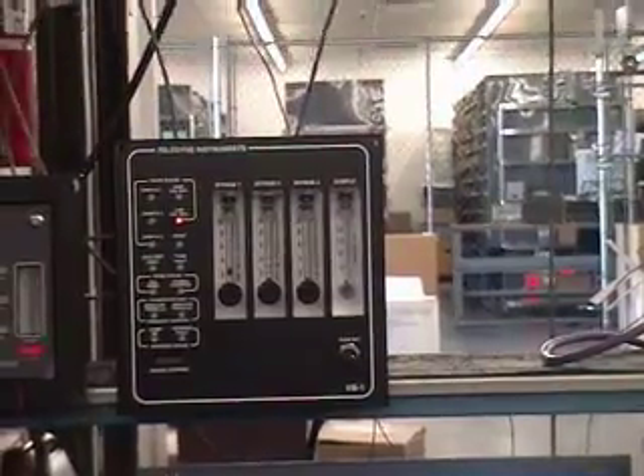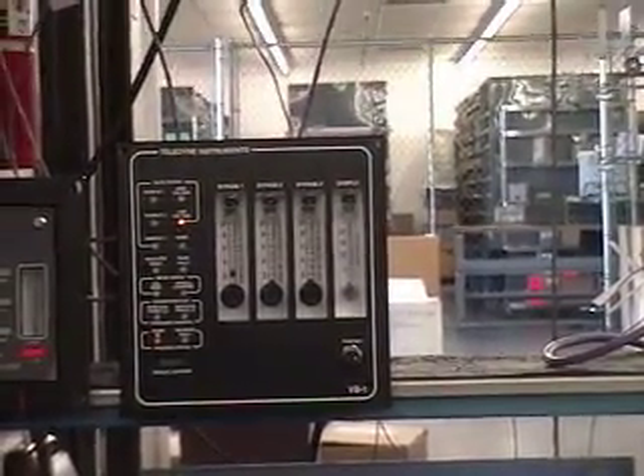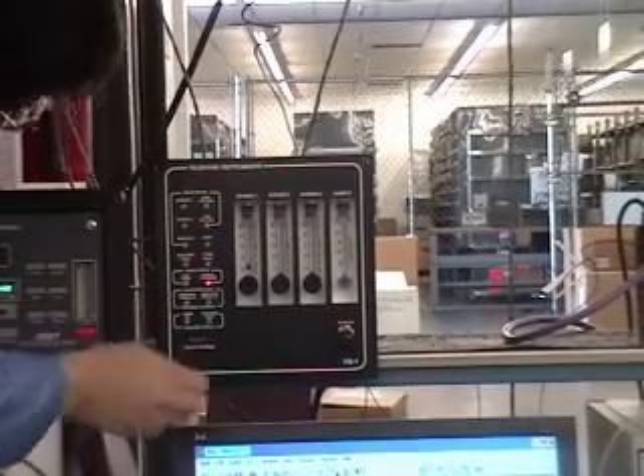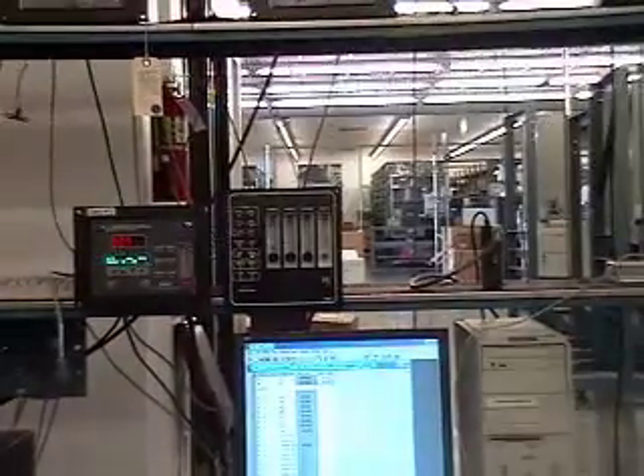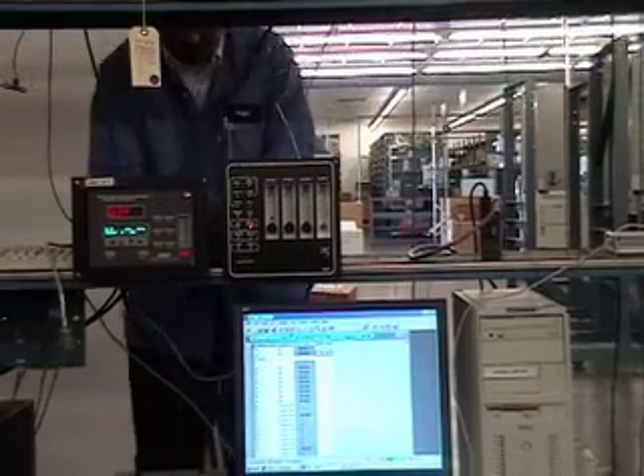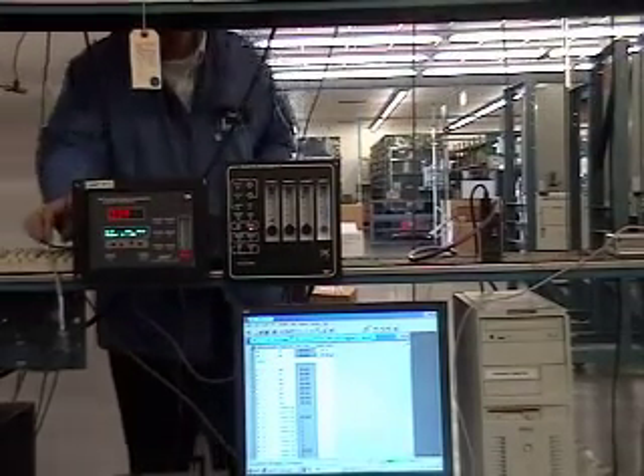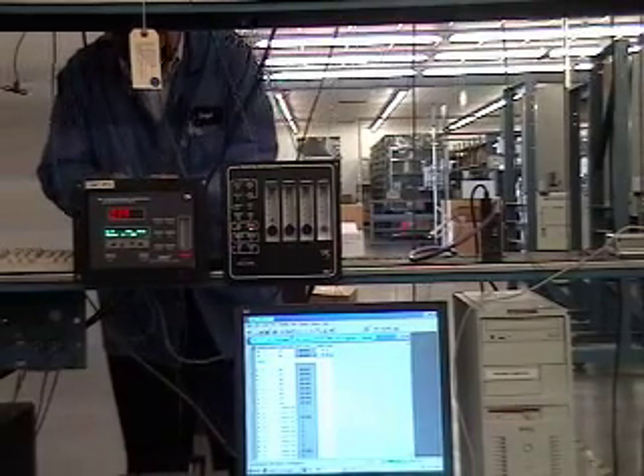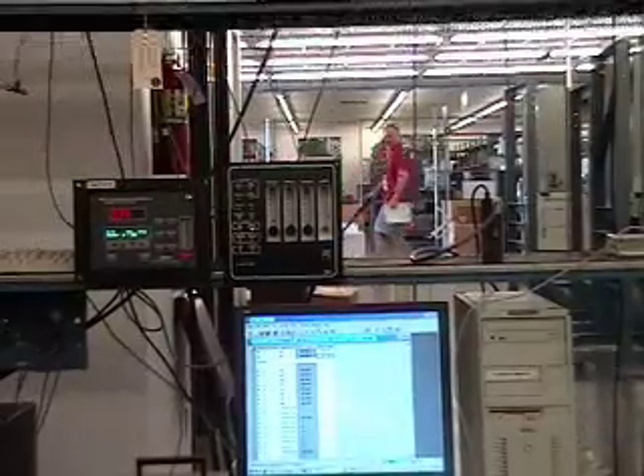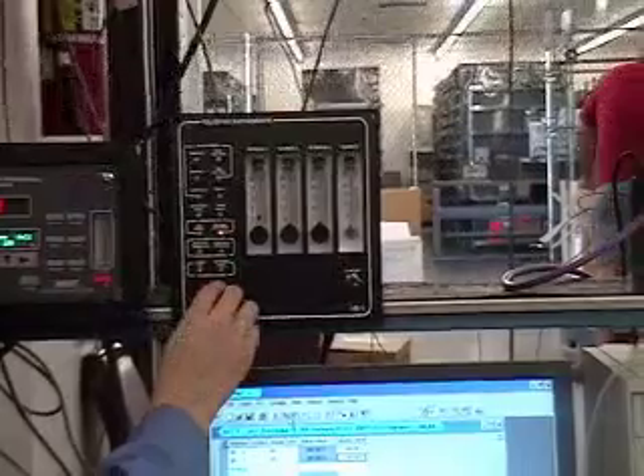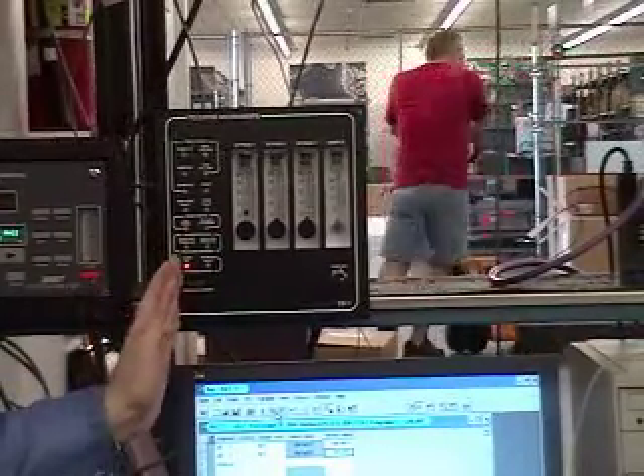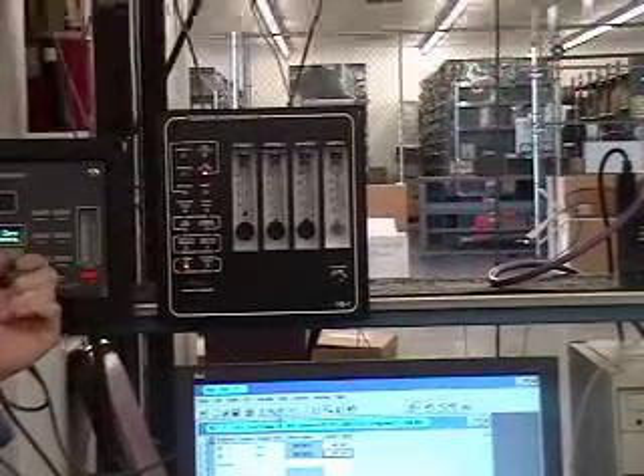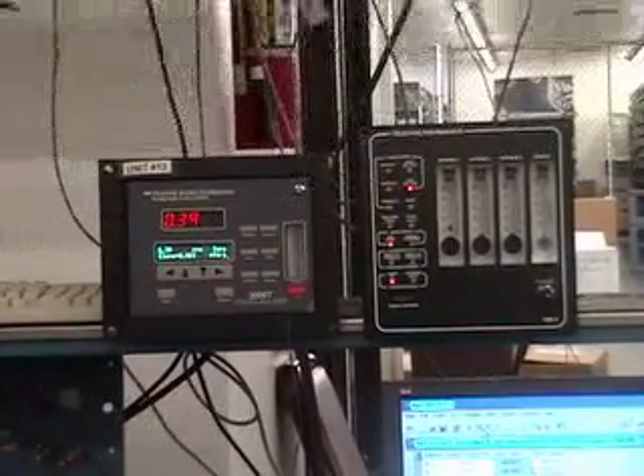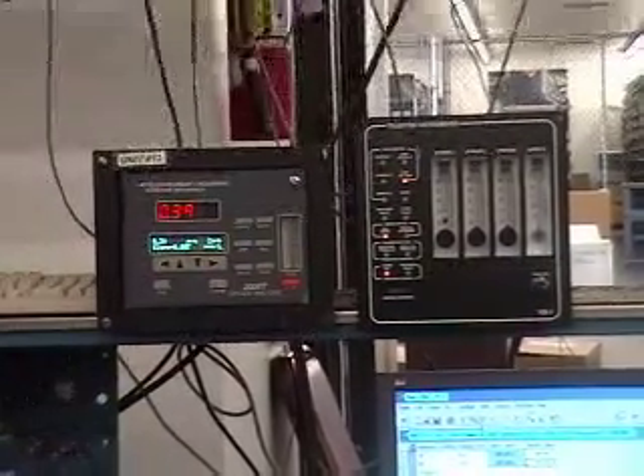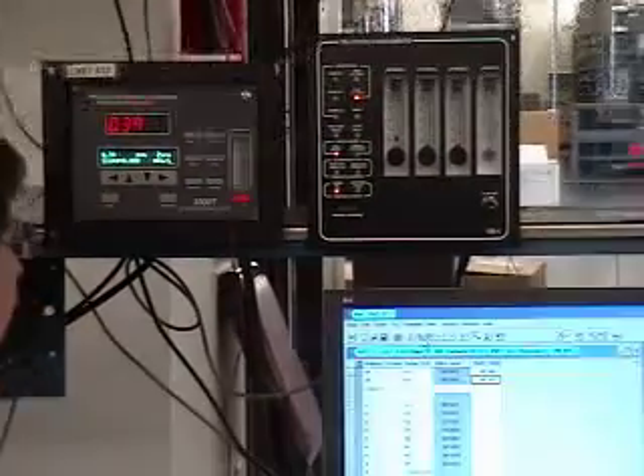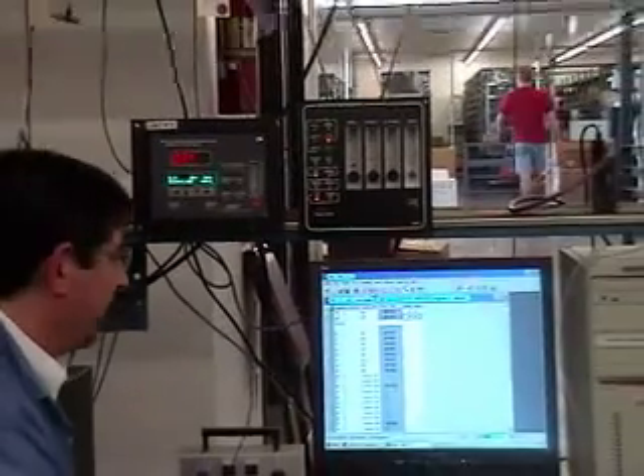Okay? Now I'm going to go back, of course, to the RS-232. I'm going to put it back in manual override, move the switch to manual override up, manual override comes on. I'm going to disconnect the 4 to 20 milliamp. I'm going to connect the RS-232 back again to the analyzer. And then bring the manual override down. And now we have the communication OK. It's solid on. So that means I'm looking at RS-232, and what do you know? The analyzer went into 0. So I have control now of the analyzer. So when the 0 is done, it's going to go back to valve number 2, which I'm trying to go to, valve number 2.